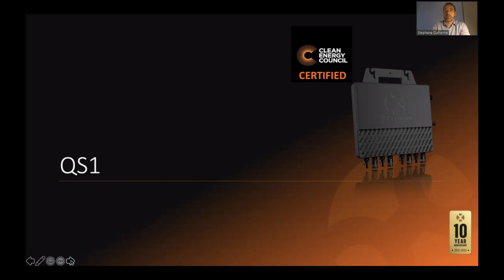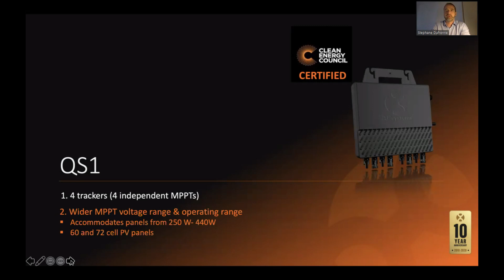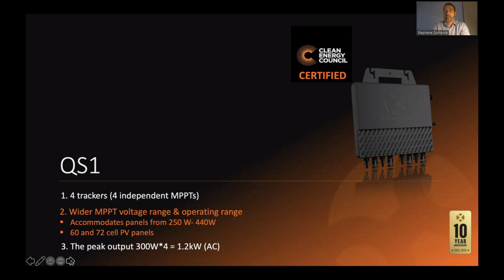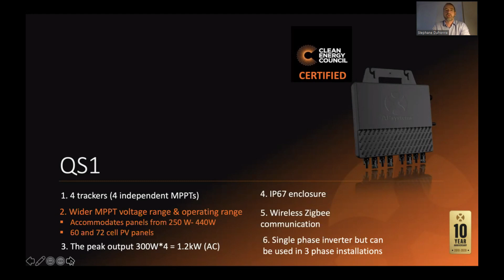In the quad phase, we have the QS1 - Q for quad, S for single, and 1 for first generation. Same characteristics as the YC600, except it has 4 MPPTs, so it's really one micro per module. Wider MPPT range, 60 to 72 cell modules are well suited, and peak output is 1200 watt AC. You can oversize the DC side by 20%, typically as you would with a string. IP67, ZigBee communication. It's single phase, but also very well suited for 3-phase installation.